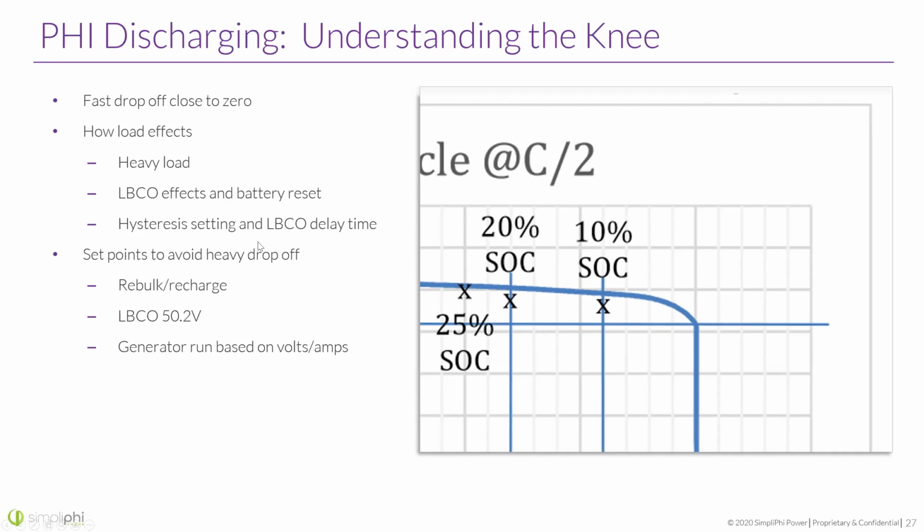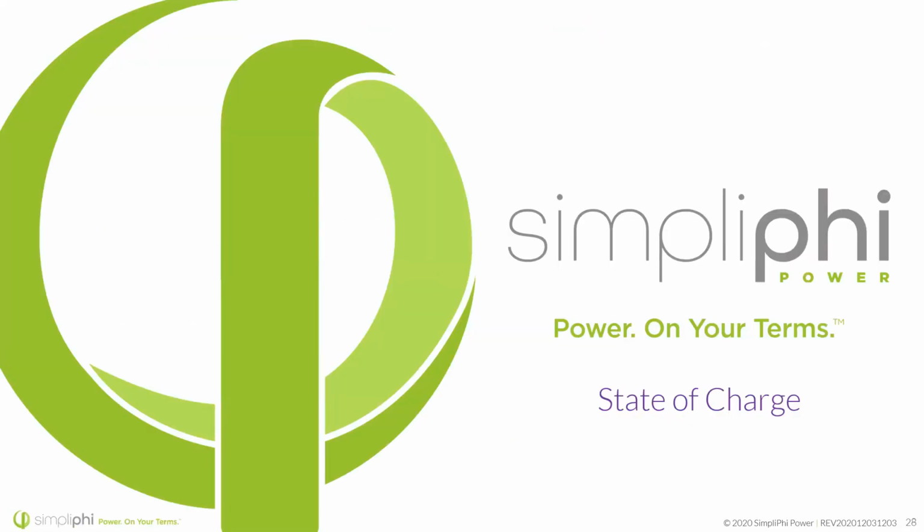There's hysteresis settings and low battery cutout delay times that are typically programmable. So you can make those a little bit more sensitive. Again, I know this is kind of confusing, but the idea is that we want the inverter's low battery cutout to disconnect and not the battery's internal disconnect. The battery's internal is there as a last resort. And once it disconnects, you actually have to get on site and reset the batteries, sometimes even charge the batteries. So we want the low battery cutout to function correctly.